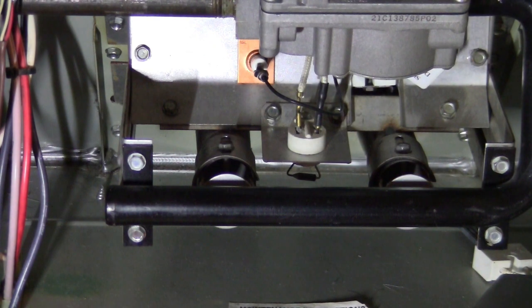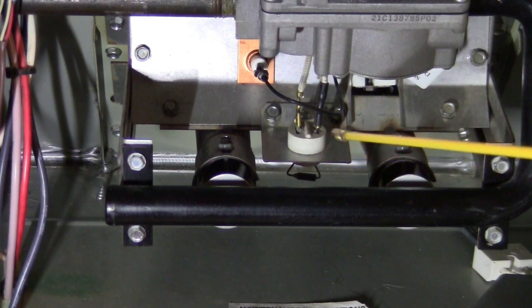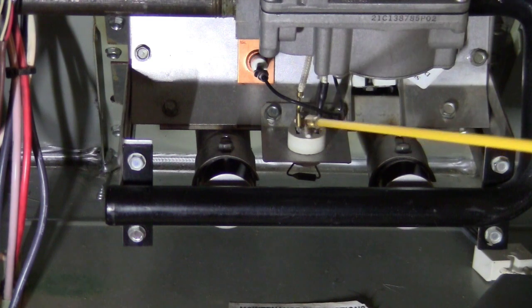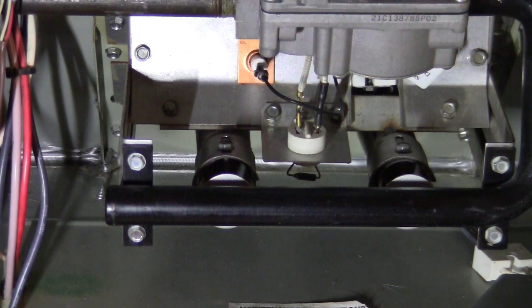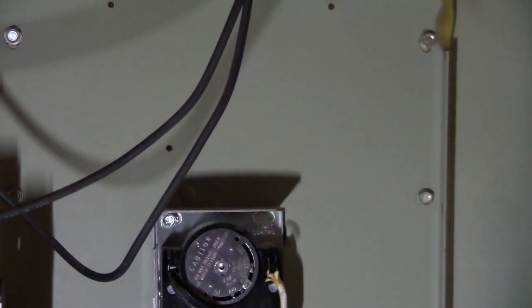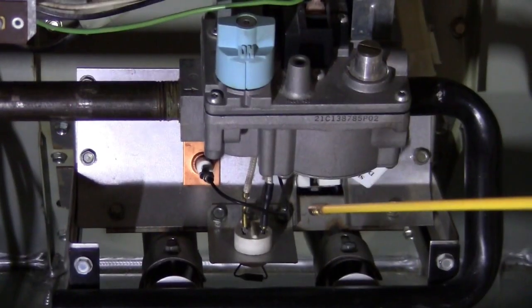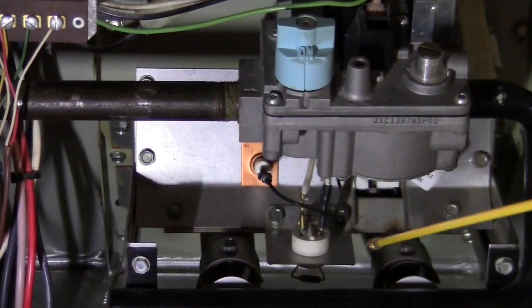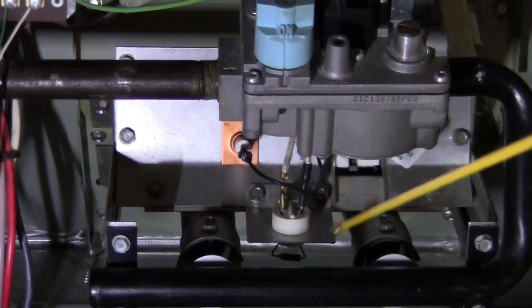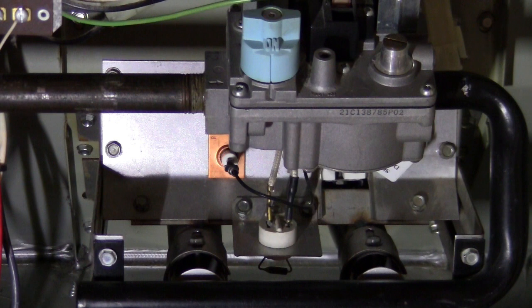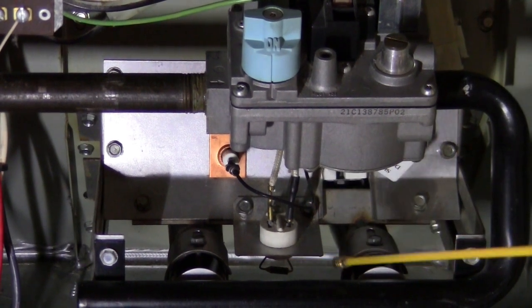What can cause that? Either the exhaust fan stops working, or some sort of air comes from outside and pushes into the inlet and the outlet ductwork. If you have very big air pressure from outside pushing against your fan and coming back down here, then you're going to blow your fire out here. When the fire is out here, it triggers this sensor, and it sends a signal to the controller. The controller kills the gas valve over here. It's going to stop the valve. So that flame overflow, or something, I forget the exact name of it, protects the flame from coming out of the burner where it's supposed to be.